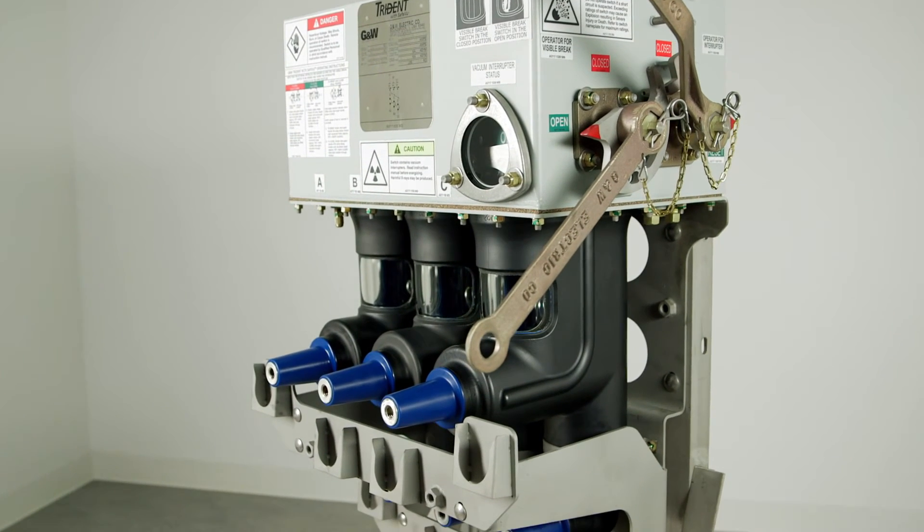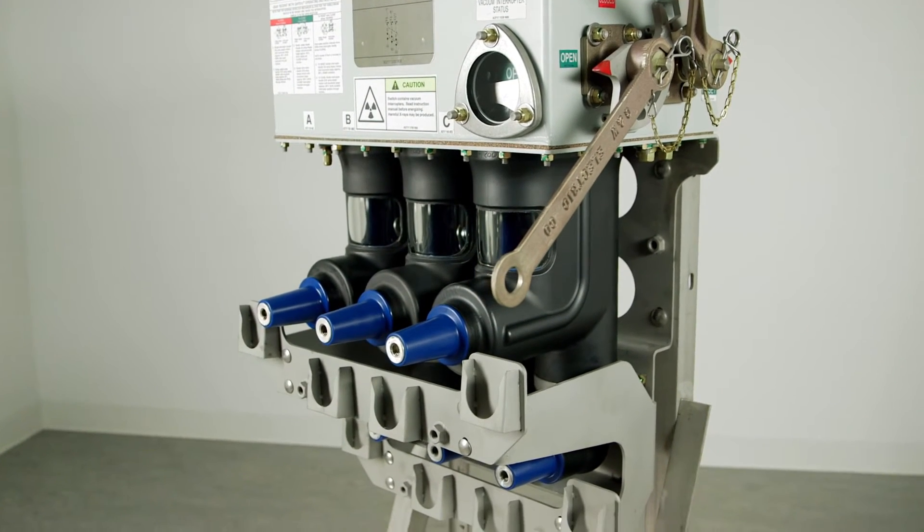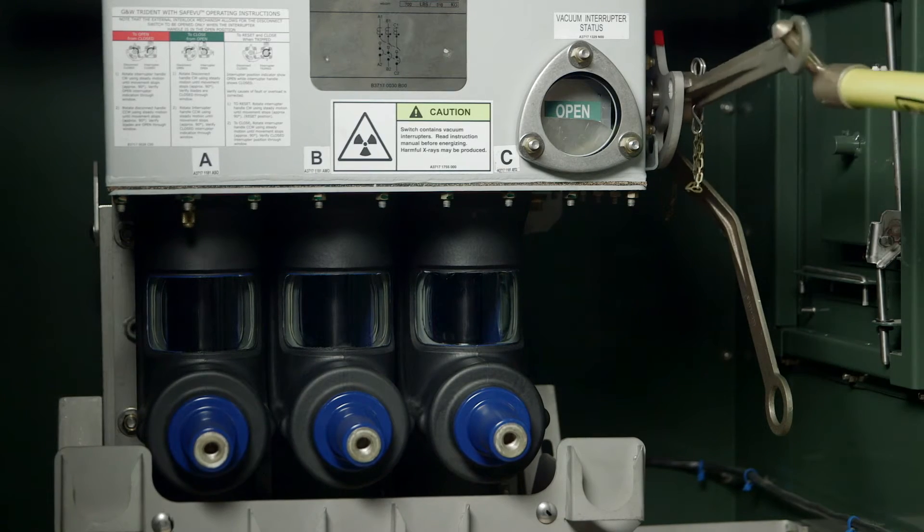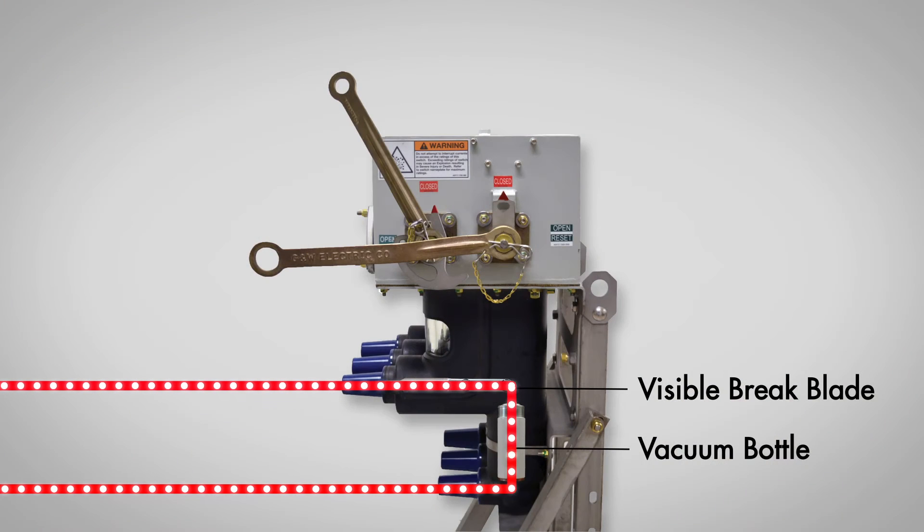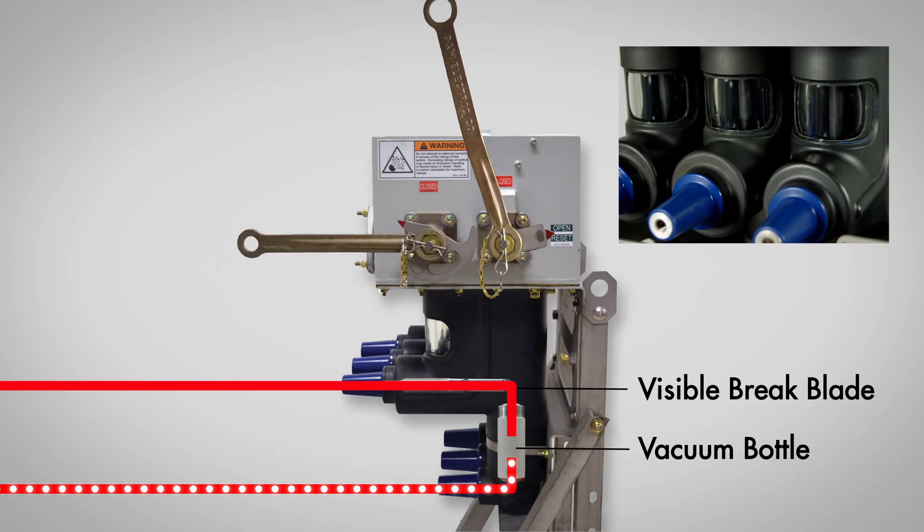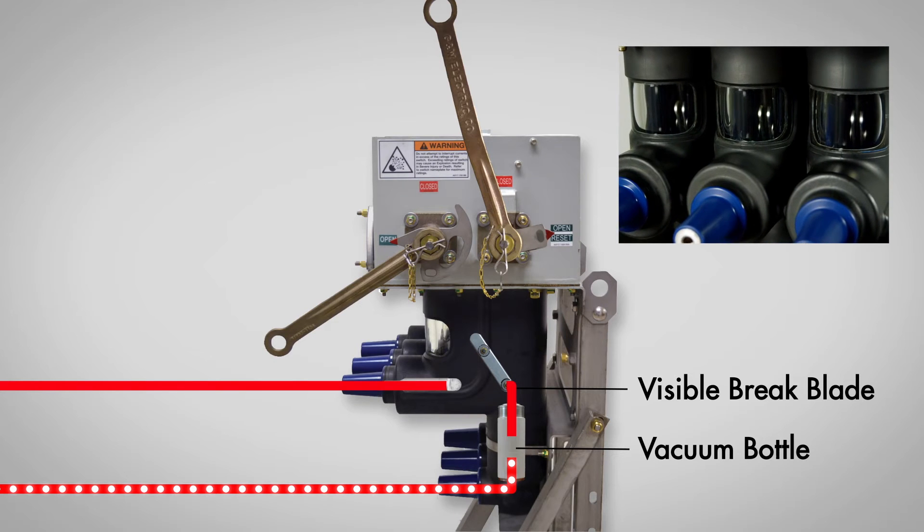Recognizing the need for visible break in solid dielectric switchgear, G&W introduced the innovative SafeView technology in 2012. By utilizing the same switch design concepts as the existing Trident solid dielectric switch line and adding a visible break blade in series with the vacuum bottle, a clear, integrated, visible break was achieved.